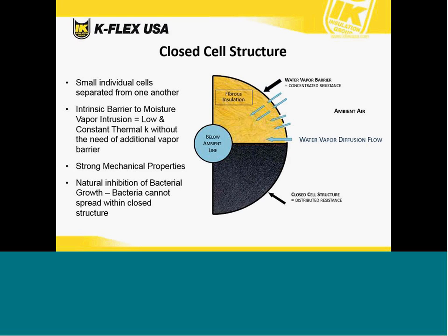So it gives us a water permeability for our products. Well, that's from our closed cell structure of elastomeric insulations. What this means is there are small individual cells with a physical barrier that are separated from one another. What gives us an intrinsic barrier to moisture vapor intrusion, a low and constant thermal K without the need of an additional vapor barrier. Also strong mechanical properties, they're physically bonded to each other, and natural inhibitor of bacterial growth.